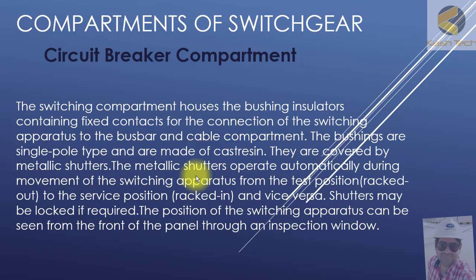Let's start our new topic: the circuit breaker compartment. The circuit breaker compartment houses the bushing insulators containing fixed contacts for the connections of switching operators to the bus bar and the cable compartment. The bushings are single-pole type and are made of cast resin. They are covered by metallic shutters, and the metallic shutters operate automatically.